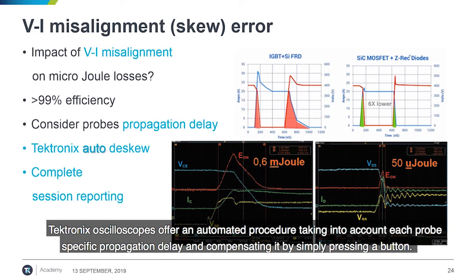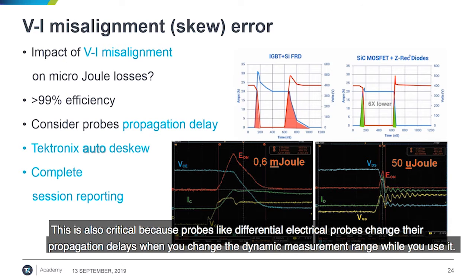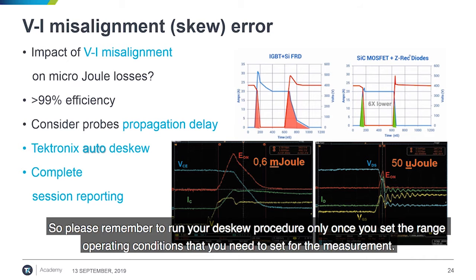Tektronix oscilloscopes instead offer an automated procedure that takes into account each probe's specific propagation delay and compensates for it by simply pressing a button. This is also critical because probes, like differential electrical probes, change their propagation delay when you change the dynamic measurement range while using it. So please remember to run your deskew procedure only once you set the range and operating conditions you need for the measurement.